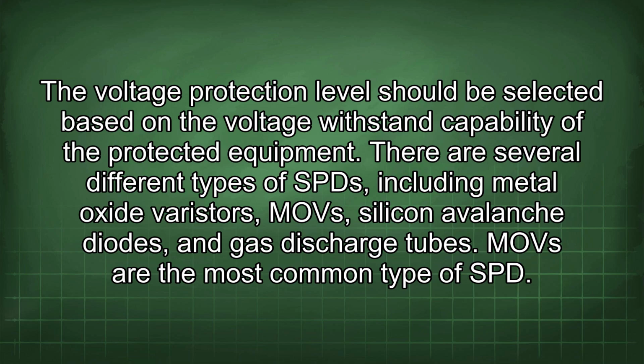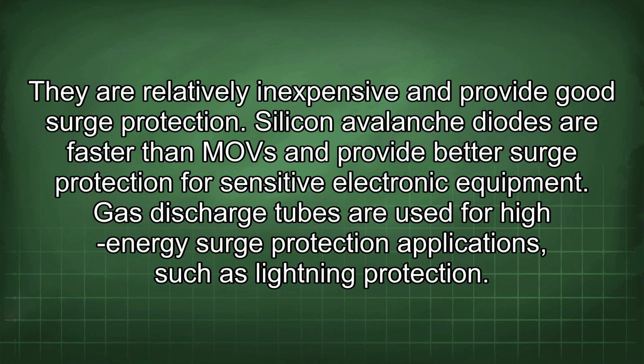There are several different types of SPD, including metal oxide varistors, MOVs, silicon avalanche diodes, and gas discharge tubes. MOVs are the most common type of SPD. They are relatively inexpensive and provide good surge protection. Silicon avalanche diodes are faster than MOVs and provide better surge protection for sensitive electronic equipment. Gas discharge tubes are used for high-energy surge protection applications such as lightning protection.